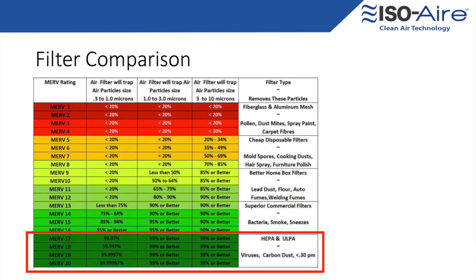Just a quick filter comparison. A lot of people ask me, well, what about MERV 13 versus HEPA? Well, since you can't put a HEPA in pretty much any of the systems except for pharmaceutical or chip makers, people are trying to get higher up with their existing systems. But as you'll see on this chart here, MERV 13 does not stack up to what a HEPA can do. It's a step in the right direction, but it doesn't do the entire job. There's still a significant number of particles getting past that filter and back into your space. Whereas a HEPA is able to capture an extremely near 100% amount of those particles.